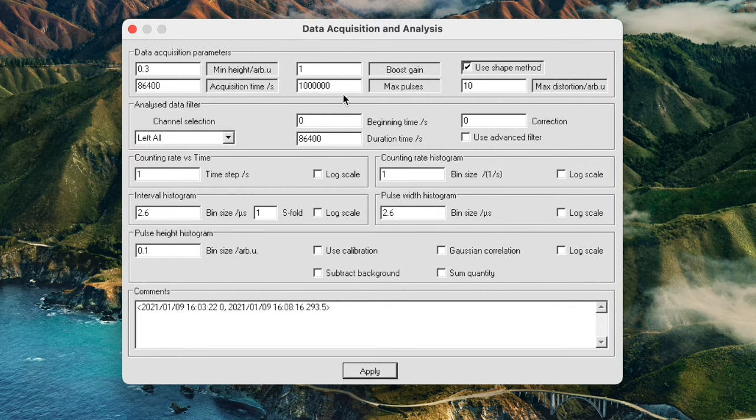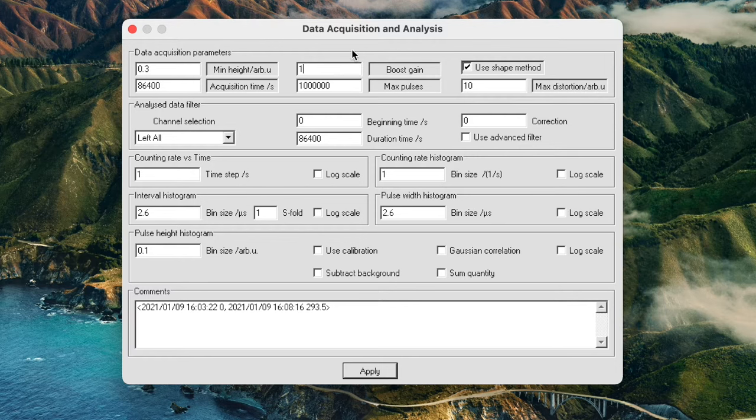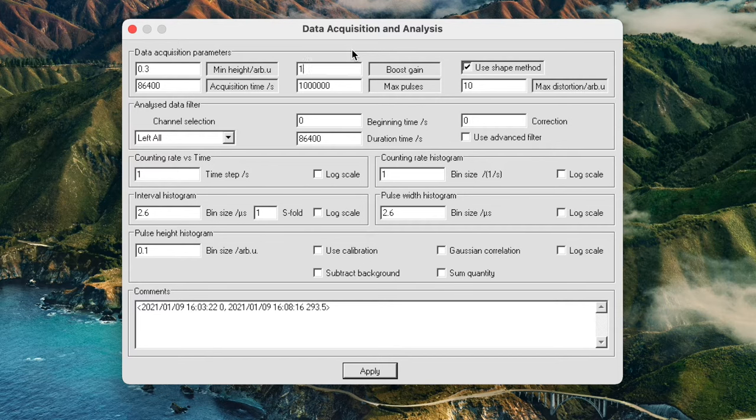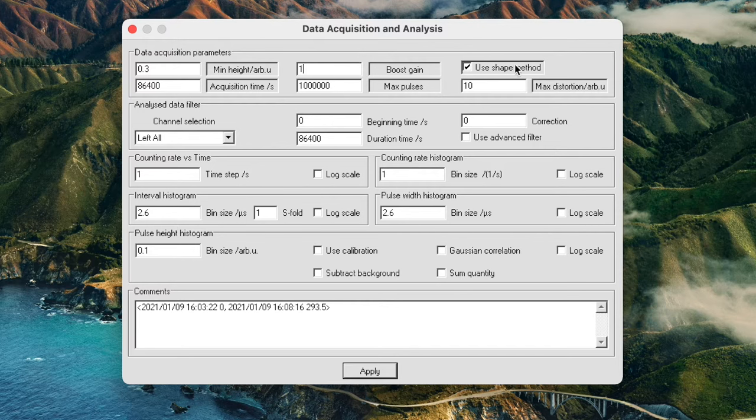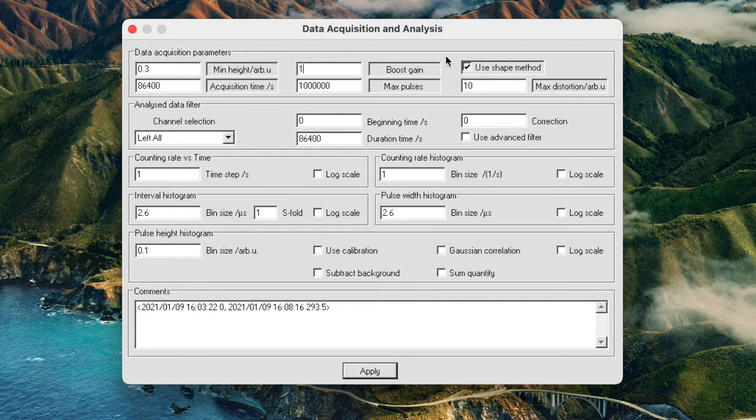The next field along here is the boost gain. In most cases that should not be necessary but if you happen to have a detector with a very weak pulse you can boost the gain here and increase the amount of gain. The next field here is very important and that is called the shape method.